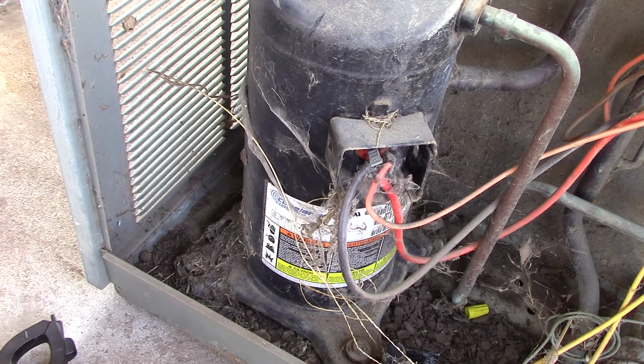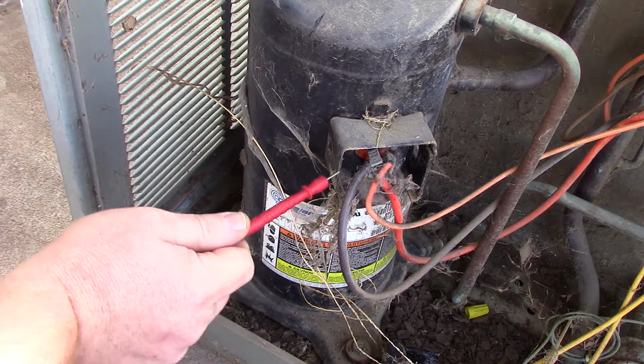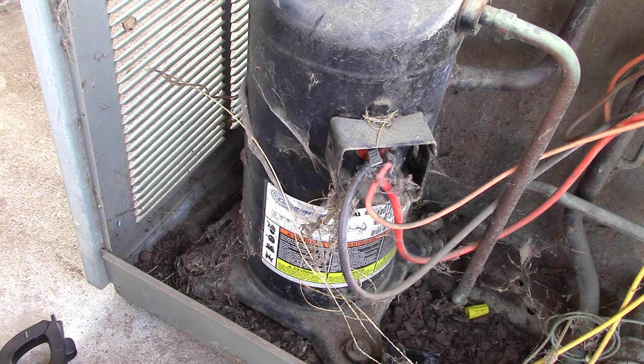Now if you go run to common, get OL, start to common, let's say 4.5 ohms, your run winding is open. It's a bad compressor. There's no fixing it. If your start to common says OL, run to common says 1.2 ohms, well, you've got a bad compressor still because the start winding is open. Ideally, in laboratory and textbook environments, your run and start windings will equal the total windings combined. So if you go R to C and get 1 ohm, start to common, S and C, let's say is 3 ohms, then when you go to R and S, you should have, well, 1 plus 3 equals 4.